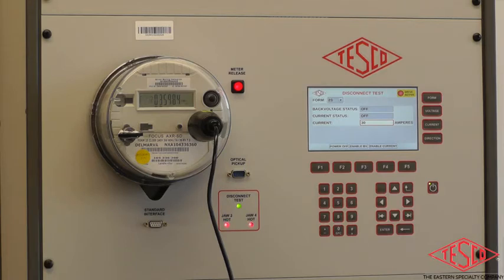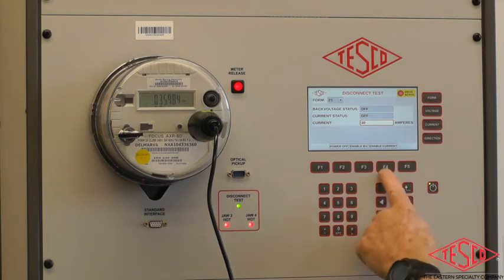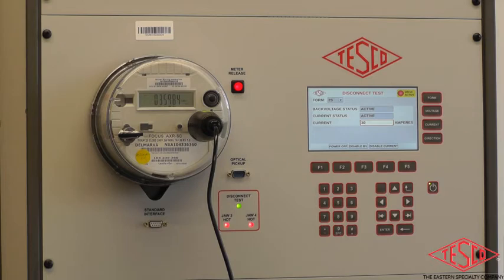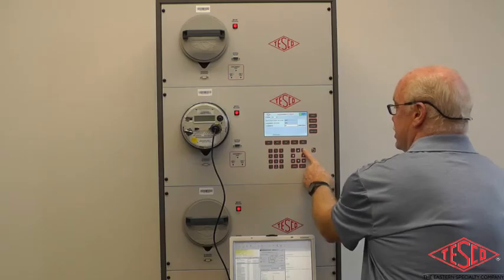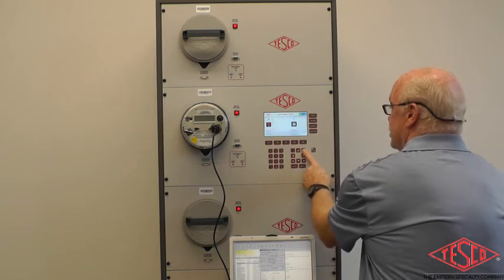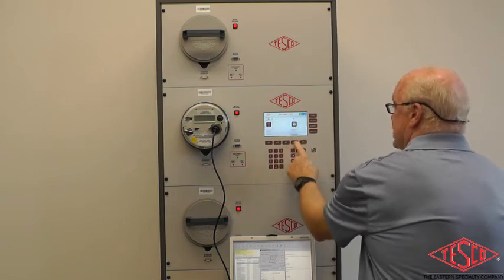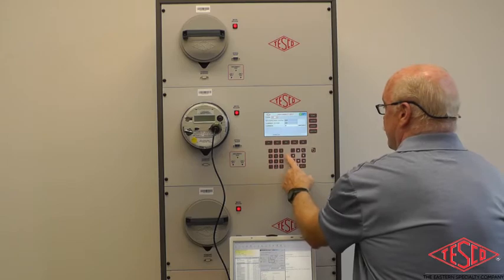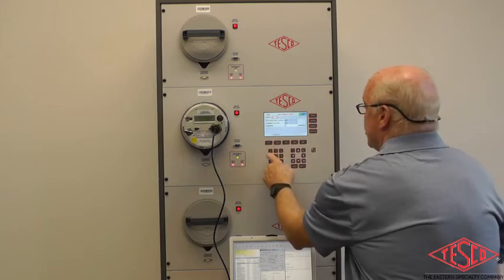So we hit close. Now it closes normally. The jaws go hot through being connected to the switch that's inside the meter. And now we can enable current again. And we have current. And now the customer is back in service. So that would be a successful disconnect test. And as always, when you move out of the screen, go backwards. And if you want to go back into disconnect, you can do it like your other forms.